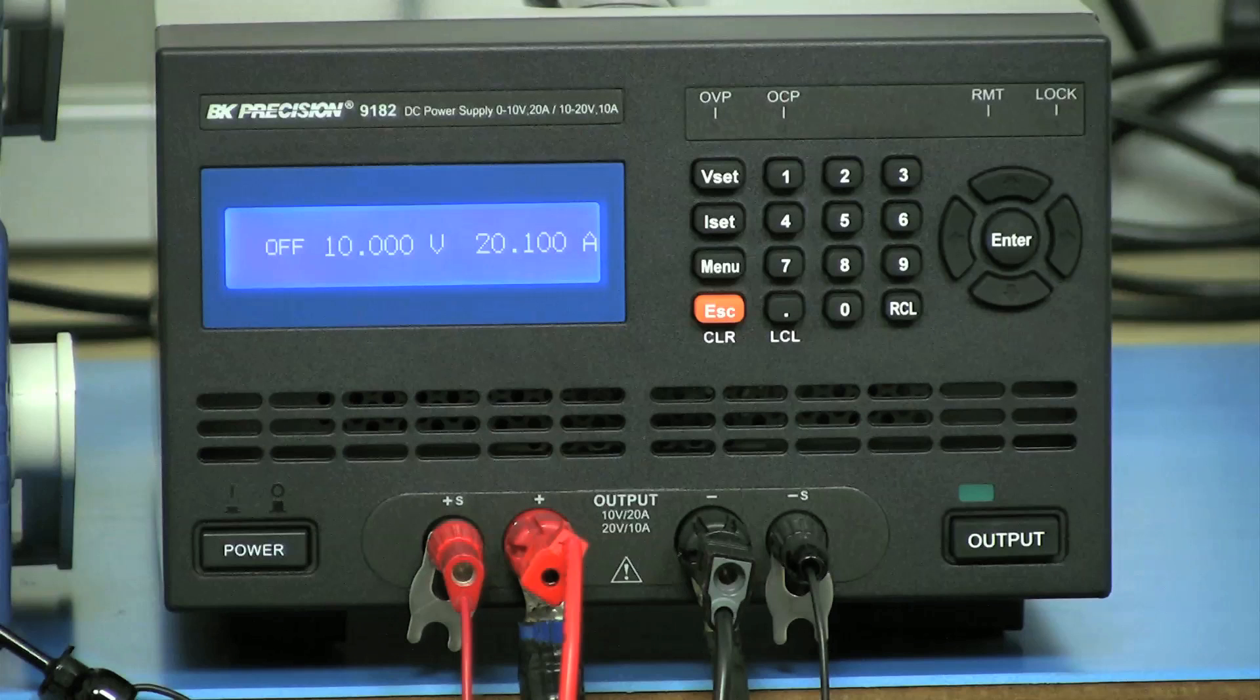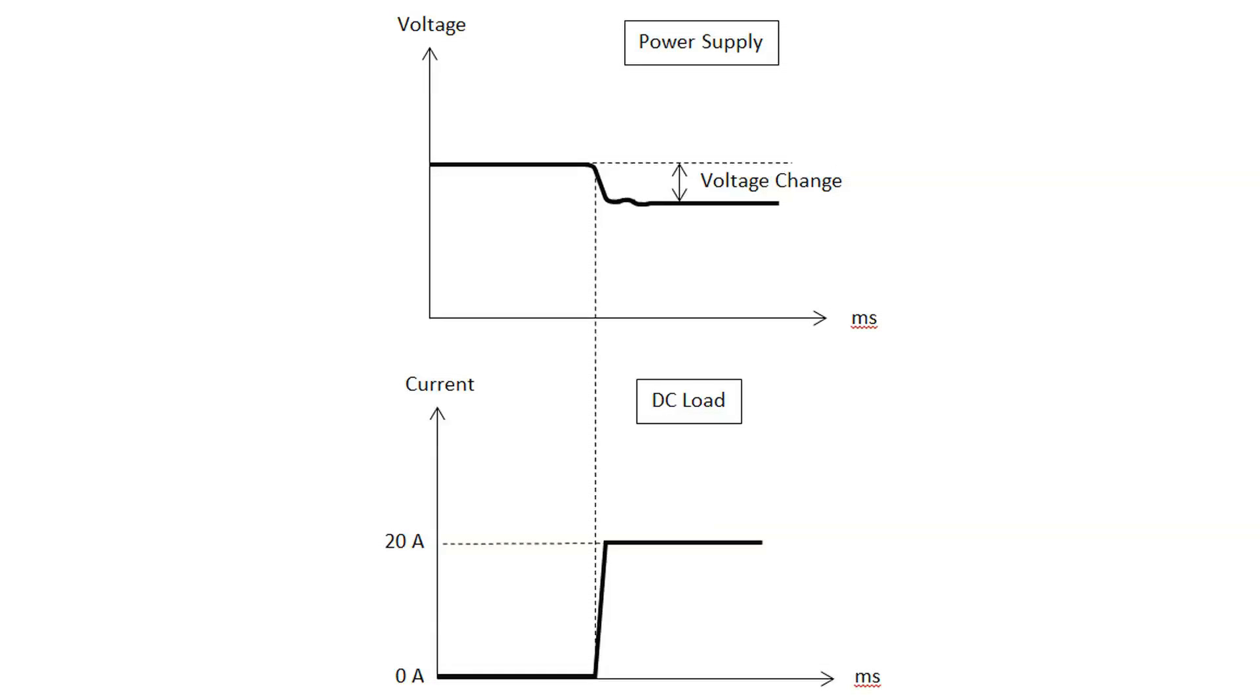With the 9182 being a constant voltage constant current power supply, I will show you how to measure load regulation in constant voltage operation. The measurement is done by measuring the change in output voltage from when there is no current load to the maximum rated current load. For the 9182, this change is from 0 amp to 20 amp.